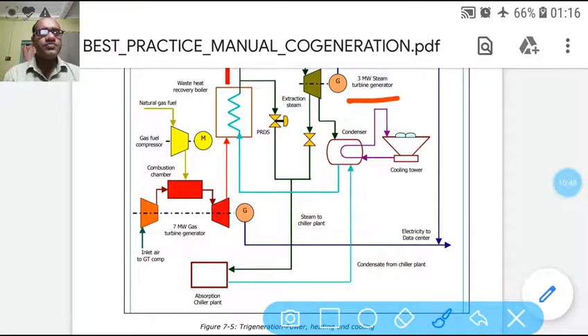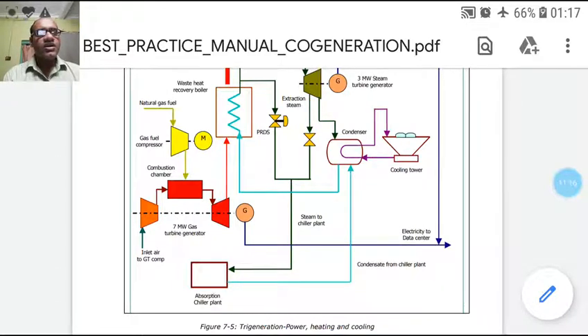Now we can see a part of the steam from the waste heat recovery boiler is going to the pressure reduction desuperheating unit, and a part of the extraction steam is also bled out, and that is going to run the absorption chiller, and that absorption chiller again is run by this condensate water. So this is about the trigeneration system.